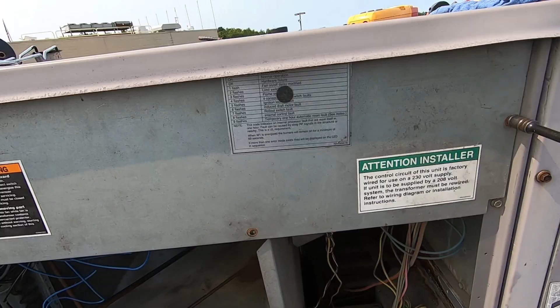Another thing real quick for you. Whenever I write up a heat exchanger, look at that, couldn't have worked out any better. Anytime I write up a heat exchanger, I always get combustion blower, flame sensor, igniter, and ignition control board. Because the last thing you want to do is come out, rip it all apart, put it all back together just to find out that the control board's bad, or the limit's bad, or the combustion blower seized up.